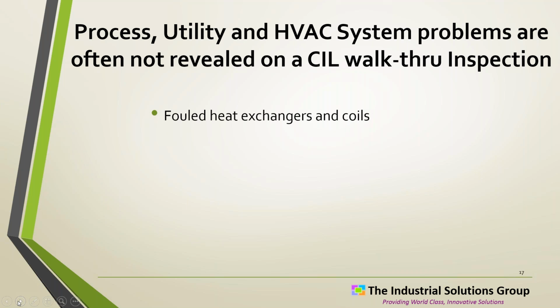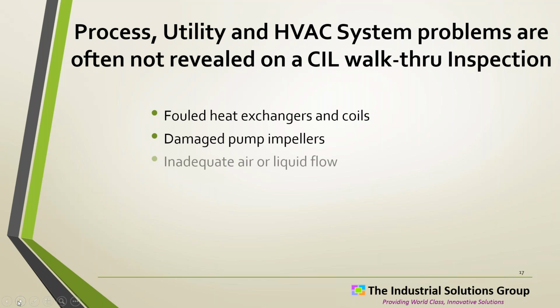Fouled heat exchangers and coils. You could have pretty nice housekeeping going on, and you could have clogged up chiller tubes because they're out of sight. They're inside the equipment and hidden from view. Pump impellers can totally get ground away with time. So your 10-inch impeller turns into a 9-inch impeller, and that pump only pumps 70% of the fluid it's supposed to. If you let it go, it'll be 6 inches pretty soon, and only 60% of the fluid will flow. You could have clogged up filter coil sections that really reduce air and liquid flows.